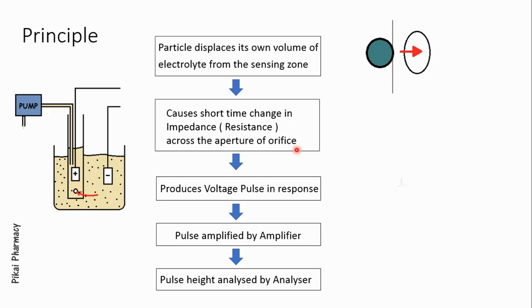Due to this change in resistance, the voltage also changes for a very short period of time as a voltage pulse. This voltage pulse is amplified by the amplifier, and then the pulse heights which are generated are analyzed by the analyzer or pulse processing units.